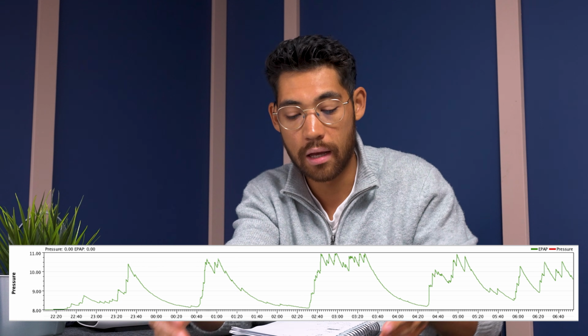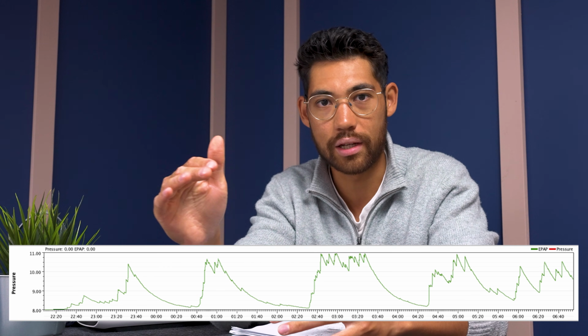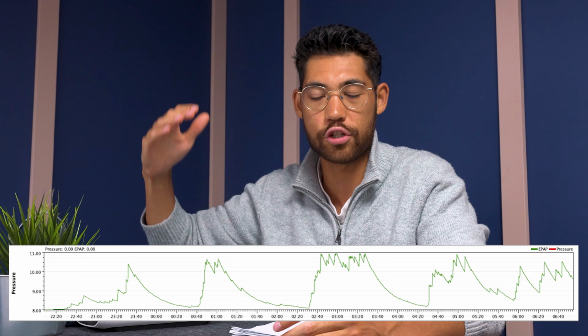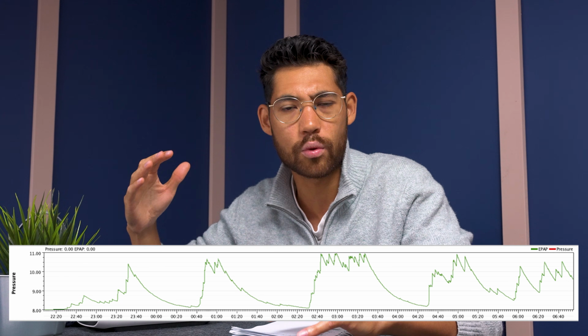And if it thinks you need it, it's going to give you the pressure of 10, because with every apnea it's going to crank up the pressure a little more. But with APAP, it's always trying to decrease the pressure—that's its main thing. It'll give you higher pressure if it thinks you need it, but after 15 minutes or so, it's going to slowly start trickling back down to the lower end of the spectrum.